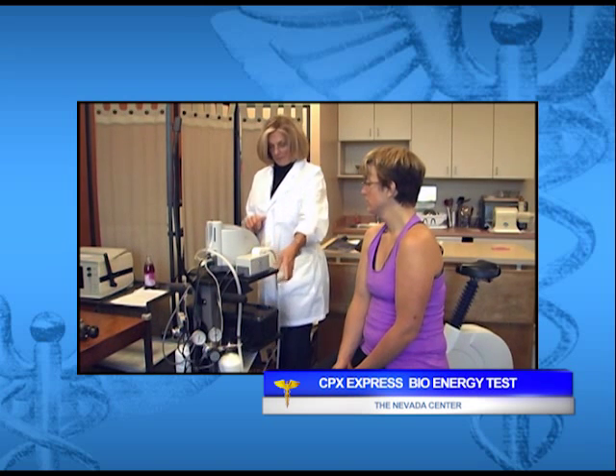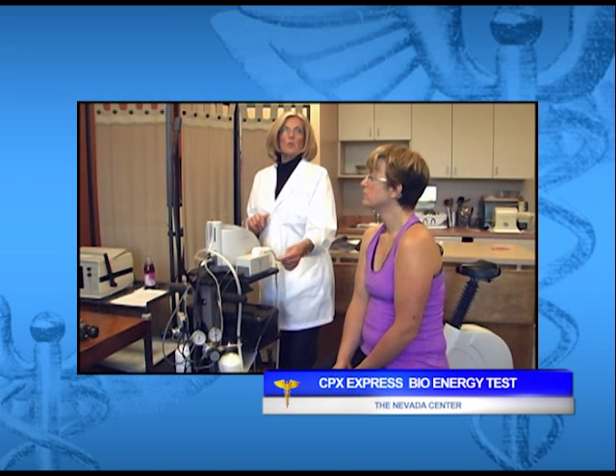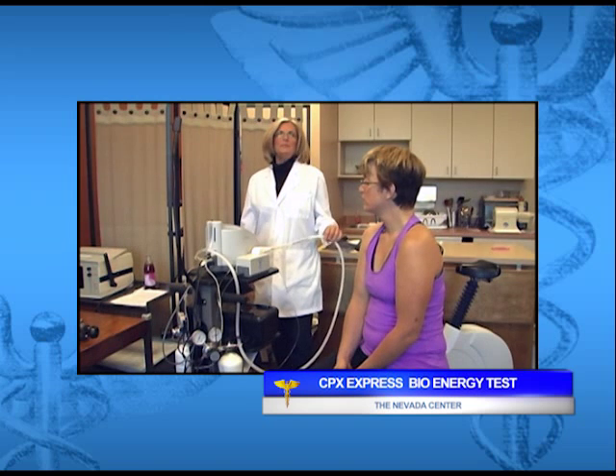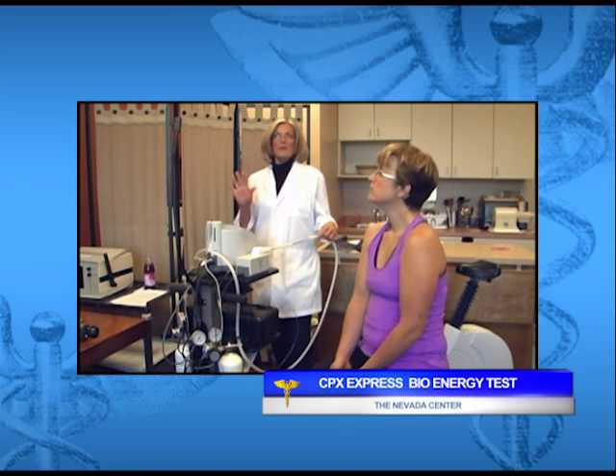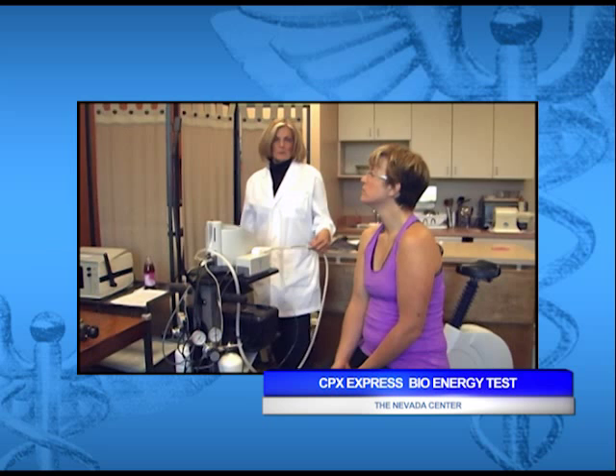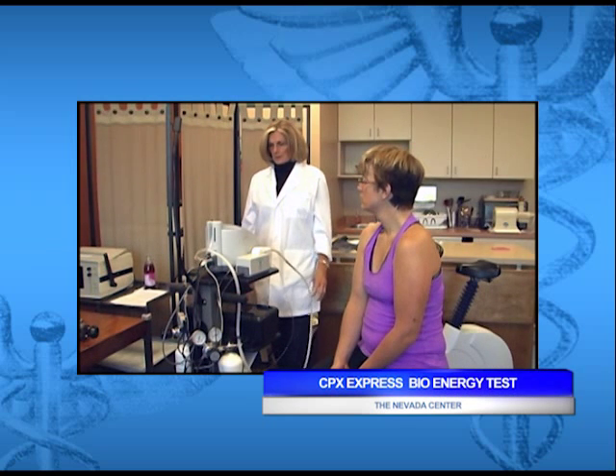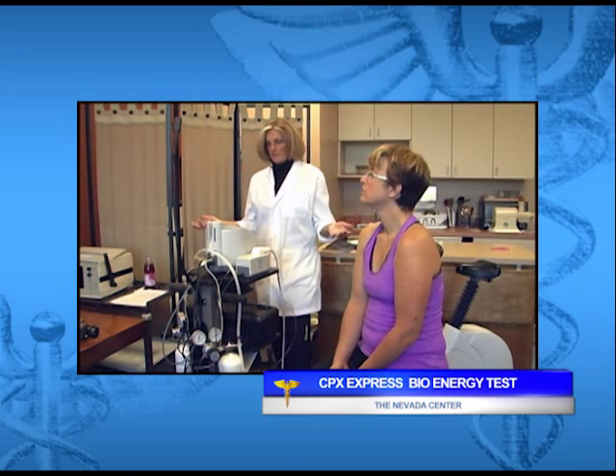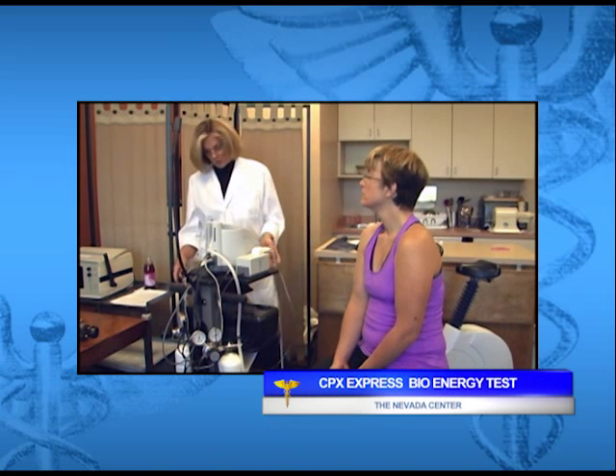These are what these lines are for. These lines should be changed once a year. The umbilical, if you don't get it wet or anything, should last you several years. So anyway, we're just waiting for it to AutoCal. It's looking good. Pressure's good in the tanks.